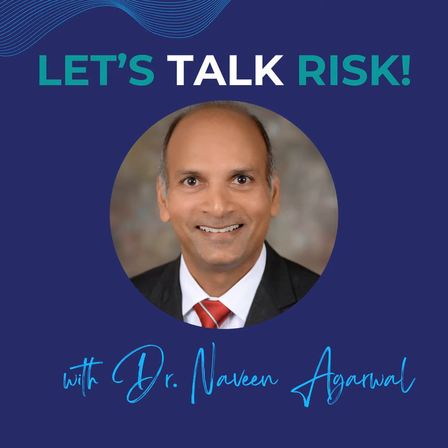So one is to follow up on Darpan's point about the risk management file references. One of the goals of the 4th edition is to have more discrete testing in the standard versus the risk management file callouts. Since it's a type test standard and not a life cycle standard, in 60601-1 we're trying to reduce the process standards or references and have more conformance requirements that are testable. So that would reduce those callouts, which then would reduce that referencing that you were talking about.